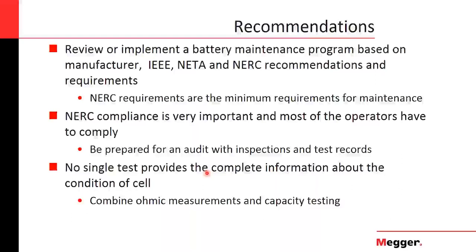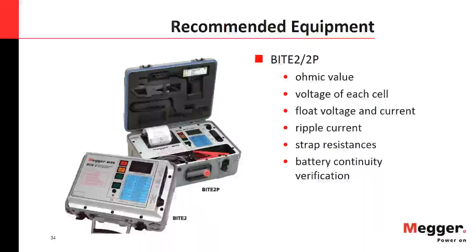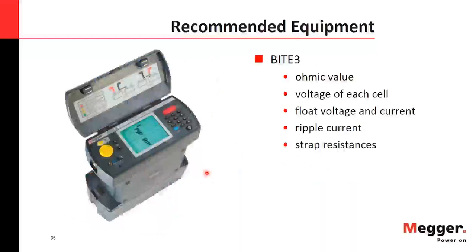There's a smaller instrument called the BITE 3 that can give you the same values except the battery continuity. However, you can measure the float current, so that is a confirmation of battery continuity. So it's an indirect battery continuity measurement. For capacity testing, you can use the Torkel 900 or 800 series. You can do a performance test, a modified performance test, or a service capacity test. And now we have the ability to measure the voltage while the battery is charging back. Some places have that in their maintenance procedures to see how the voltage behaves when charging back.